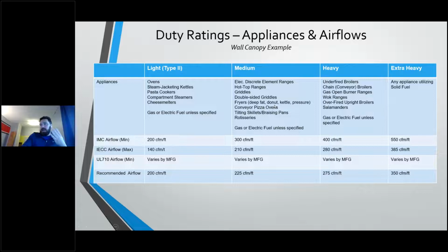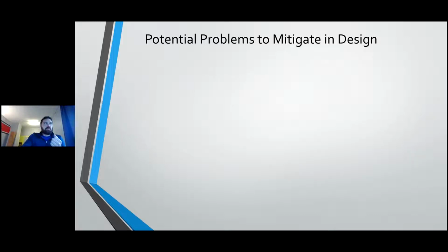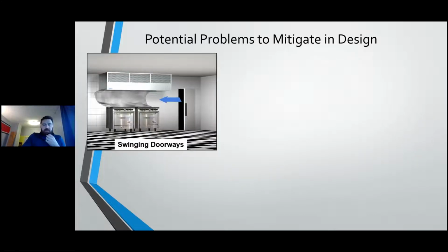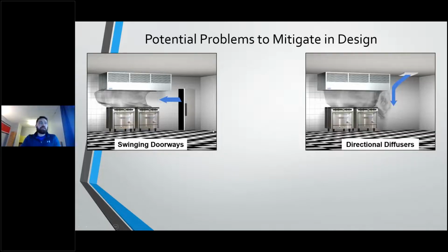So we know our CFMs, we have an idea of what our grease duct is going to look like, and what problems can we run into? There's really only a couple. Biggest one, you want to keep an eye out for wherever there's swinging doorways, or high traffic areas around the hood that could potentially either push or pull air into or out of the capture tank of the hood. The other one that's most easy to control, in my opinion, is the utilization of directional diffusers. So it's best practice to not have any directional diffusers within a kitchen space so that you're not accidentally throwing air back towards the hood and causing any turbulence under that hood.